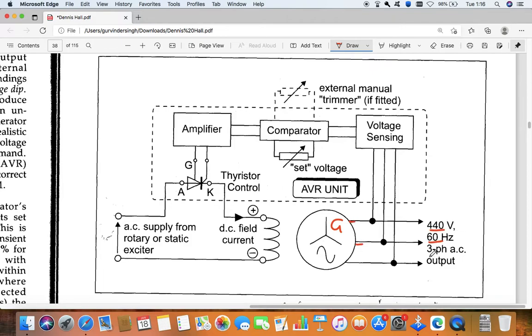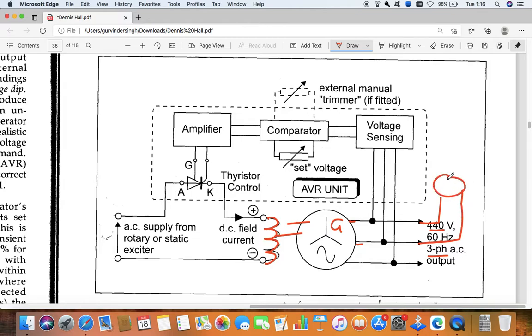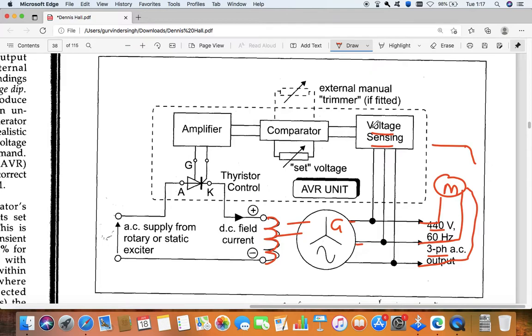From the DC field coil, it is creating a field, and that is cut by the conductor because the rotor is the rotating part and the EMF is produced here. Now let us consider we have one motor here - a 3-phase motor or single-phase motor, whatever it is. So what will happen? The voltage dip will happen. When the voltage dip occurs, this voltage dip is taken care of by the voltage sensing sensor - it will sense that a voltage dip is there, and it will send a signal to the comparator.